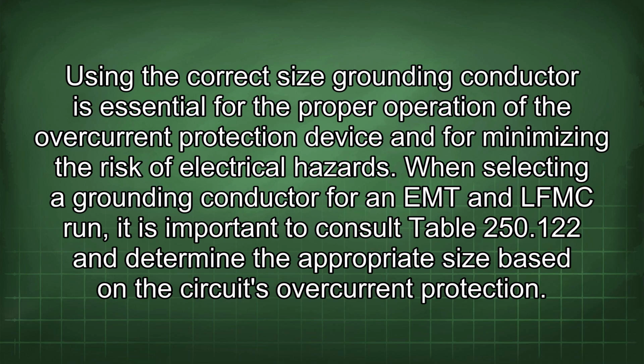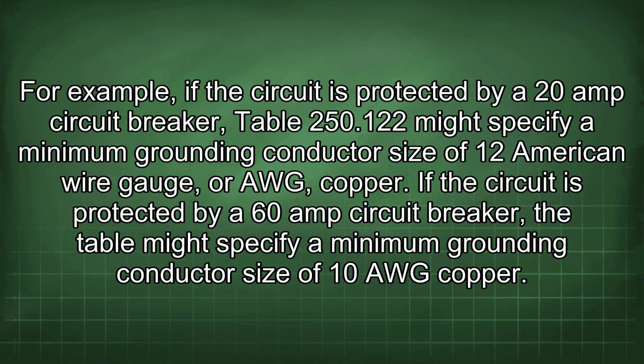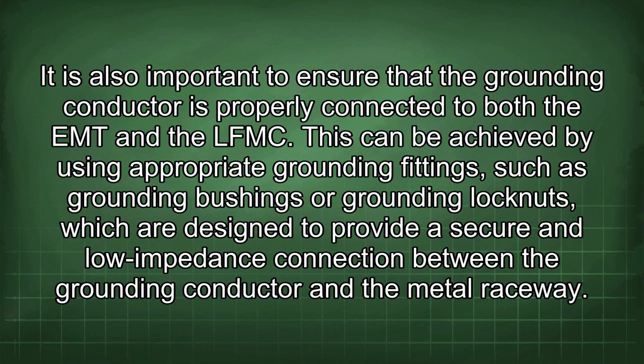When selecting a grounding conductor for an EMT and LFMC run, it is important to consult Table 250.122 and determine the appropriate size based on the circuit's overcurrent protection. For example, if the circuit is protected by a 20-amp circuit breaker, Table 250.122 might specify a minimum grounding conductor size of 12 American wire gauge, or AWG, copper. If the circuit is protected by a 60-amp circuit breaker, the table might specify a minimum grounding conductor size of 10 AWG copper. It is also important to ensure that the grounding conductor is properly connected to both the EMT and the LFMC. This can be achieved by using appropriate grounding fittings such as grounding bushings or grounding lock nuts, which are designed to provide a secure and low impedance connection between the grounding conductor and the metal raceway.